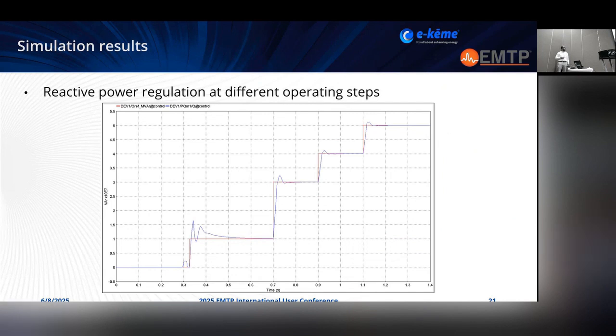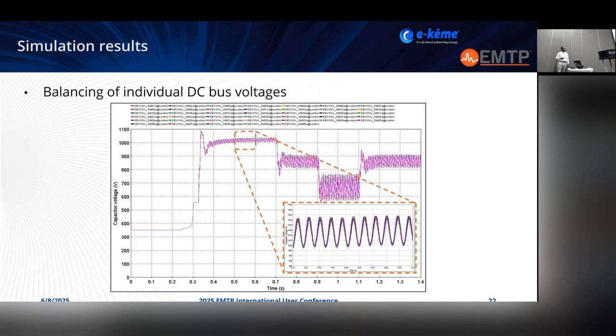Now we can see the simulation results of the system. In this case, it's the reactive power response at different operating steps. In these graphs, we observe the response of the system to different changes in the reference signal at different moments. We can see that the system behavior is stable in the different sequence of steps. And another important result is the balancing of the individual DC voltages.